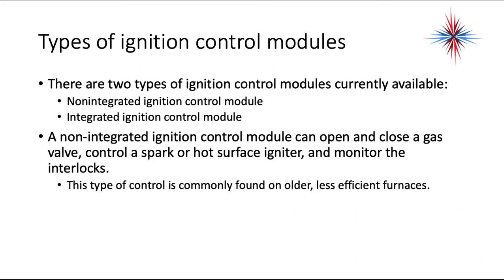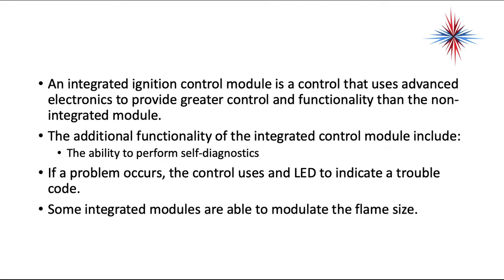There are two types of ignition modules currently available. We have a non-integrated control module, and we have an integrated control module. A non-integrated ignition control module can open or close a gas valve, control a spark or hot surface igniter, and monitor the interlocks. This type of control is commonly found on older, less efficient furnaces.